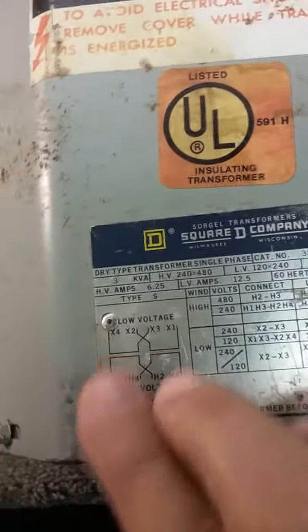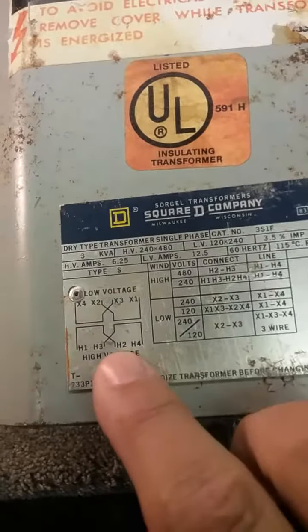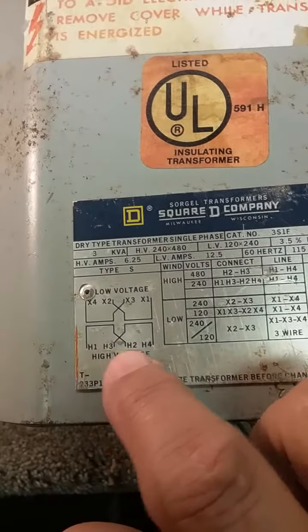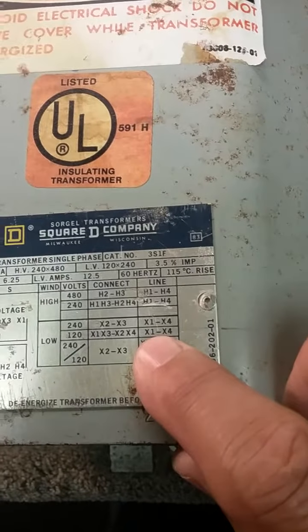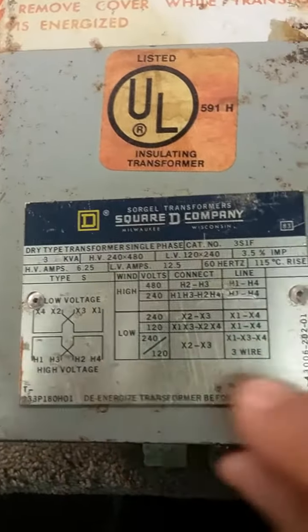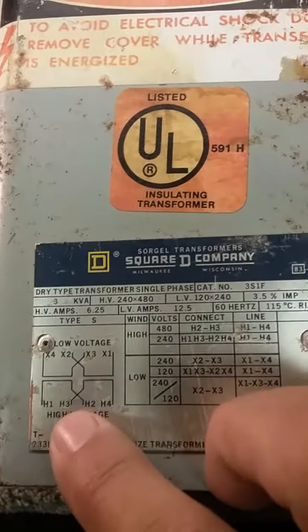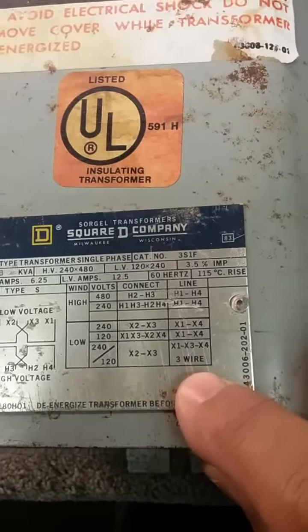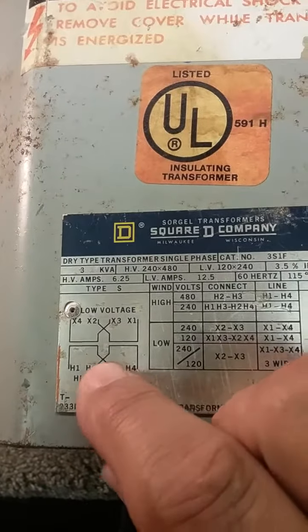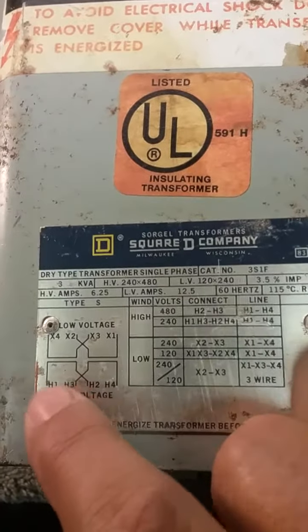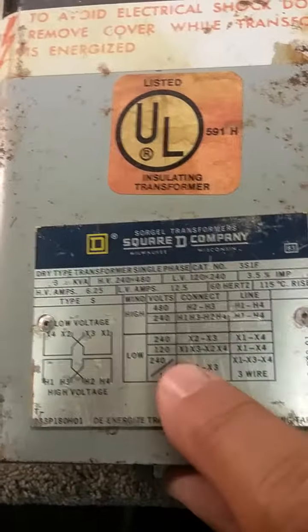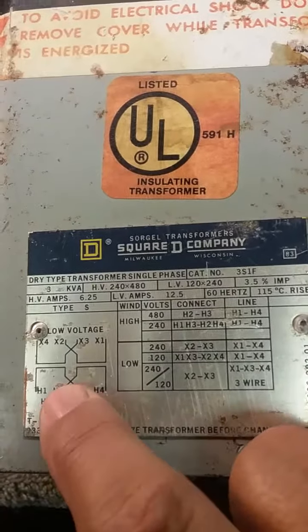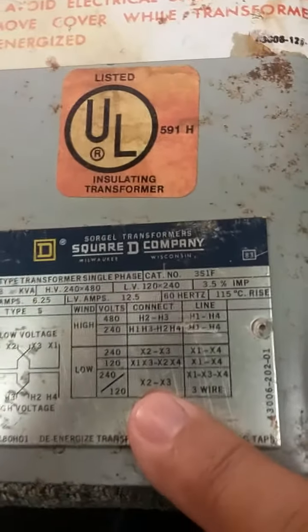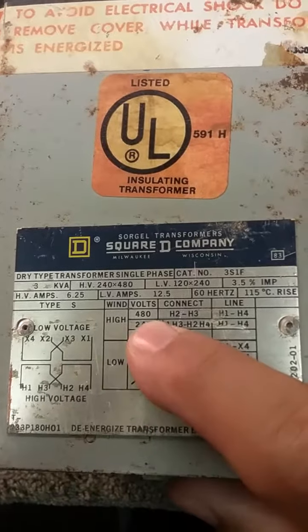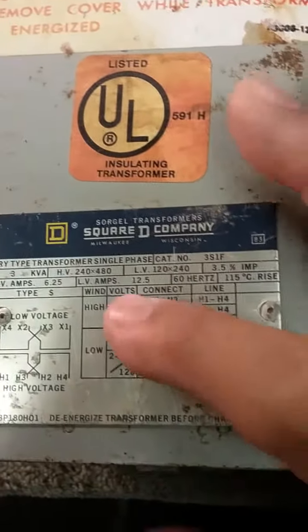By tying these two secondaries in parallel, tie H1 and H4 together, H3 and H2 together, pull your load off X1, I'm sorry, not X1 and X4. So, of course, here and here, I'm sorry, you can cross X1, X3, and X4 using a 3-wire line, and you can put a neutral here and have a hot here and a hot here, and pull out 240 across the whole thing, or 120 across either leg. So you get that option by tying these two together. That would be running 240 in. So it can even be a 1-to-1 match.